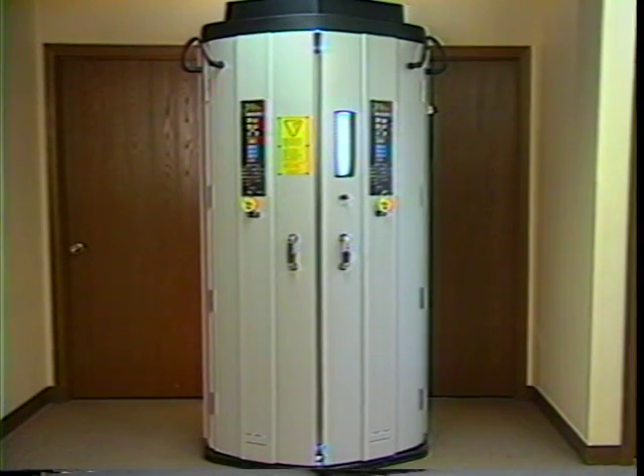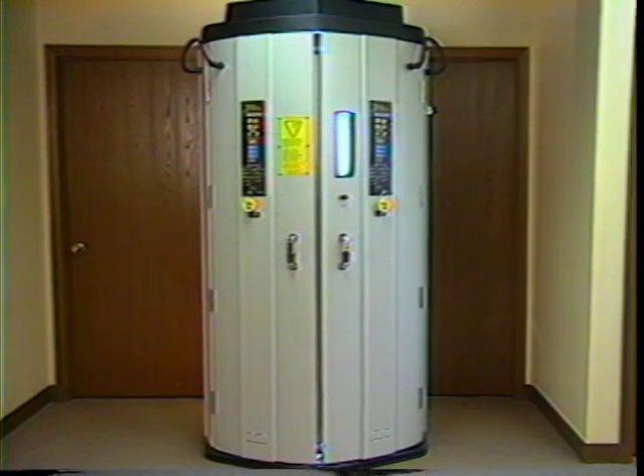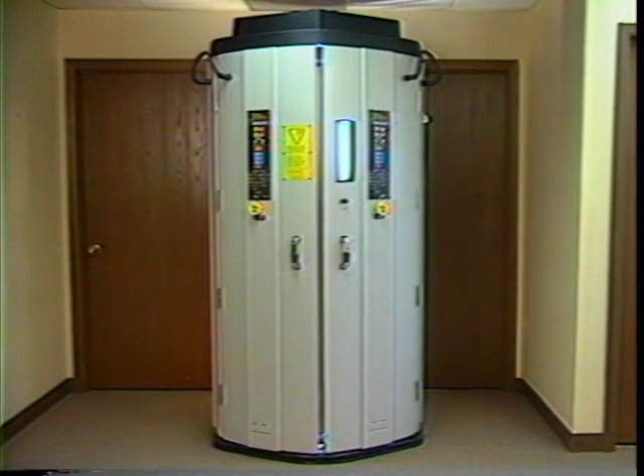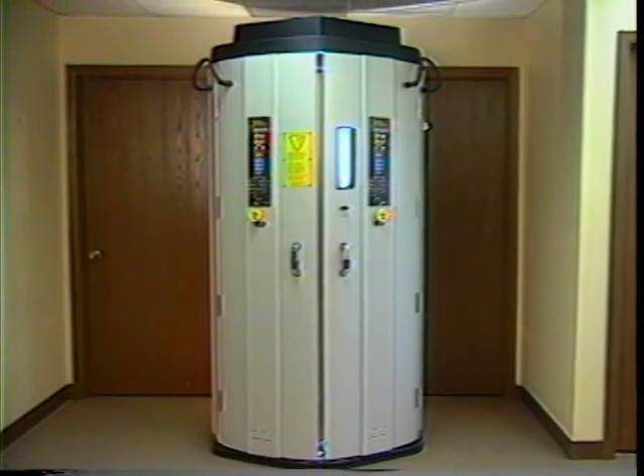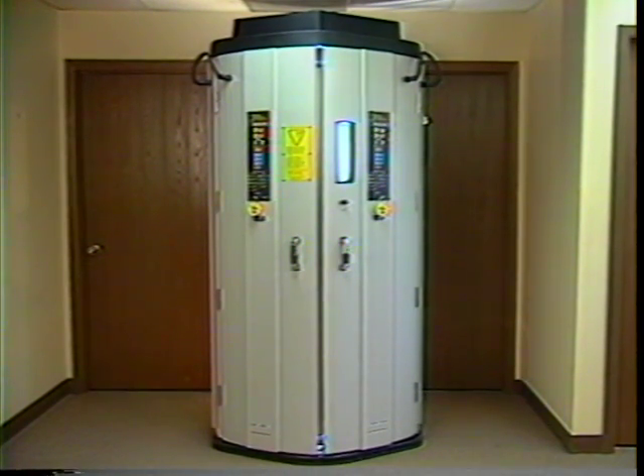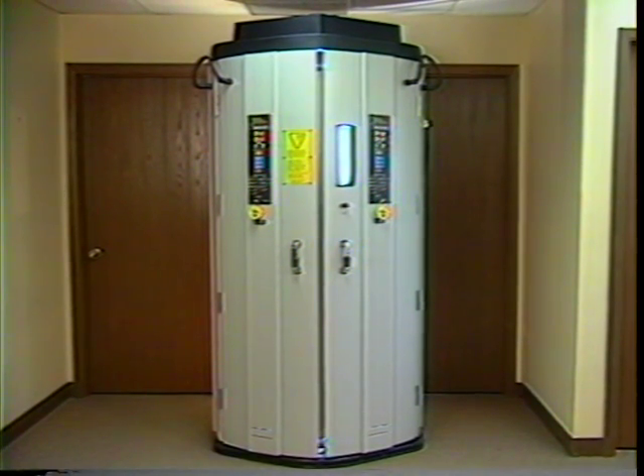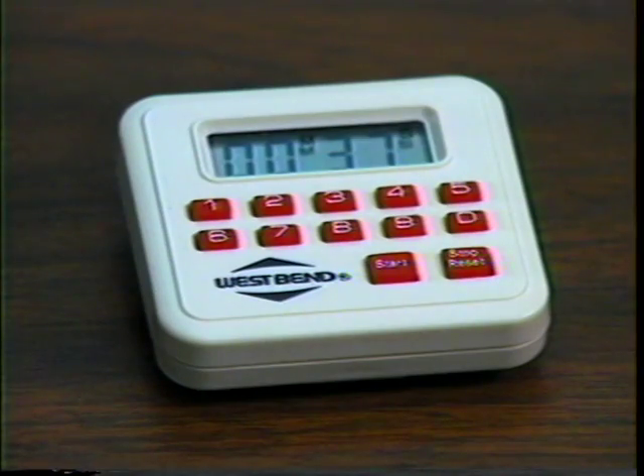The HOUVA II system is a state-of-the-art phototherapy device, employing the highest quality control components available. Although it is relatively simple to use and operate, only trained personnel should operate the device. Also, be certain that the HOUVA II is connected to a dedicated earth ground to protect the sensitive solid-state electronic components, as well as the patient and operator against electrical shock. And never allow the device to be used without a trained attendant present to monitor the patient at all times during treatment. Finally, do not forget to use the small handheld backup timer as a precaution against the potential of a component failure.